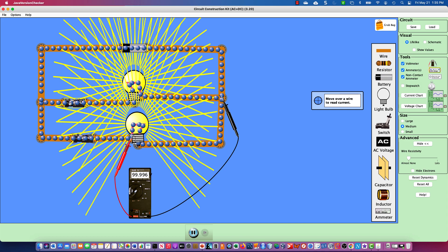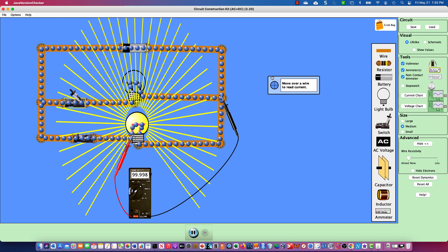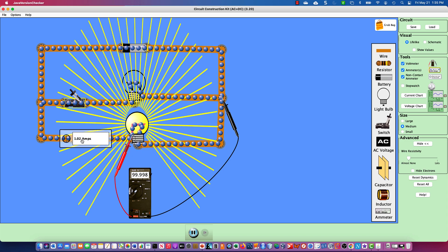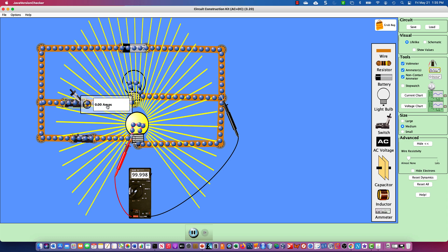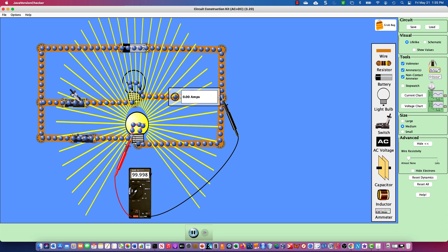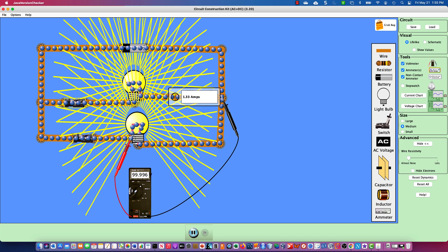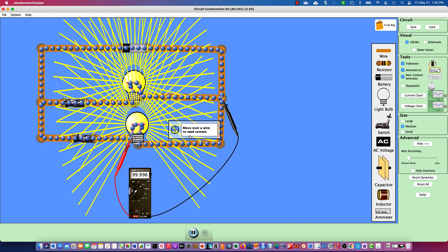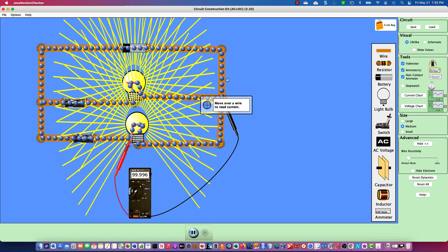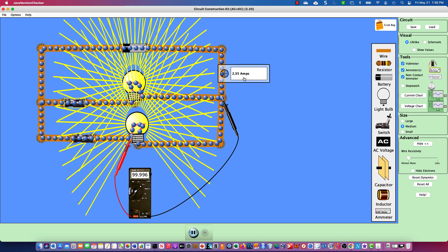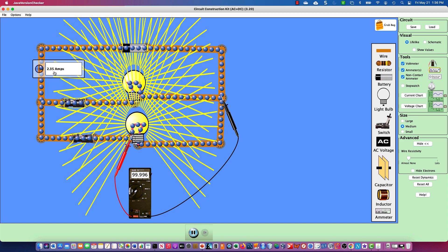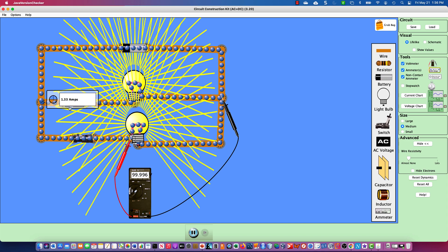If I open switch one and take my amp clamp, I now have 1.02 amps — and no matter where I go in the circuit that's running, I have about 1.02 amps. In the circuit that's not running because switch one is open, I have zero amps. When I close switch one, that branch gets 100 volts. I now have 1.3 amps in the top leg and 1.02 amps in the bottom leg, coming to a total of about 2.35 amps — because amperage adds in a parallel circuit.